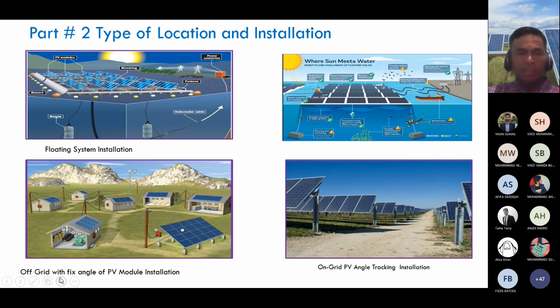But there is another type of installation, called fixed tilt angle, meaning you cannot adjust the angle of the PV module. Before installation, the designer or engineer will consider how much the PV module angle needs to be for that area, based on software like PVsyst. That software can calculate the optimal tilt angle to get the maximum power generation from the PV module.